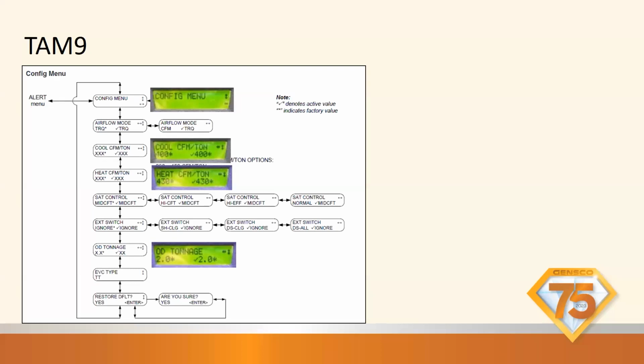I don't know why they put 430 on this slide. You want it at 400 CFM per ton, especially for variable speed outdoors. For charging, it has to be at 400 CFM per ton. And then if we need to increase the airflow for operational reasons, sometimes we do, you still have to charge at 400 because that's where the charging chart is set for. Then you can change your airflow on variable speed if you need to, okay? For heat pumps, standard heat pumps, 400 CFMs, that's where you want it set, okay?